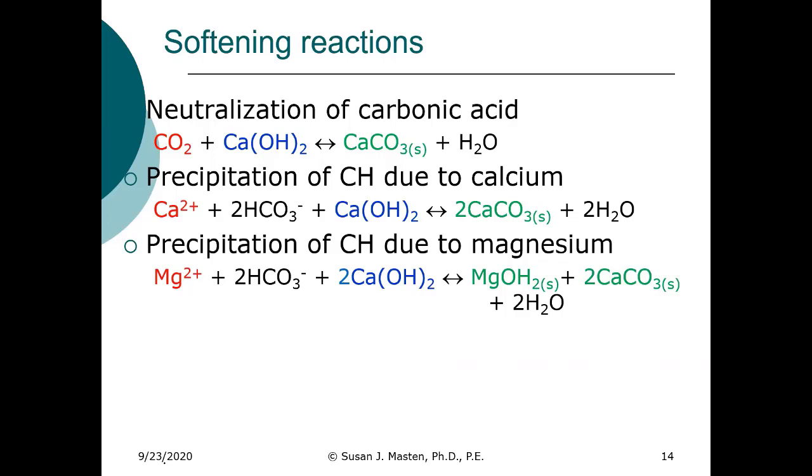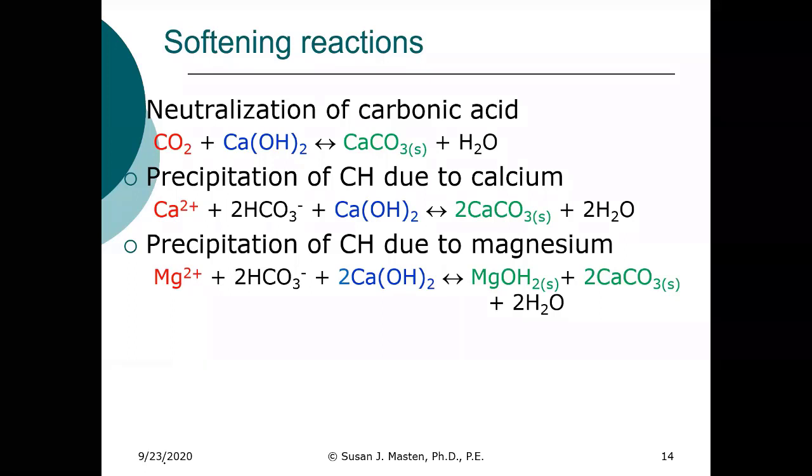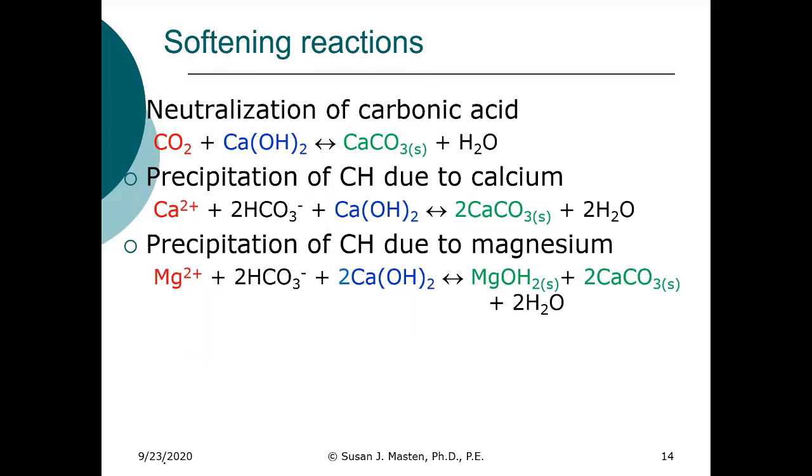So these are the reactions that occur. As I mentioned, it's a significant amount of chemistry. But if you simply think about it as balancing an algebraic reaction, hopefully it becomes a little more straightforward and less challenging. So as I mentioned, groundwaters will often contain CO2. So the first reaction that we need to do is to neutralize that CO2. We get no, notice here, we get no hardness removal. We're simply increasing the pH.